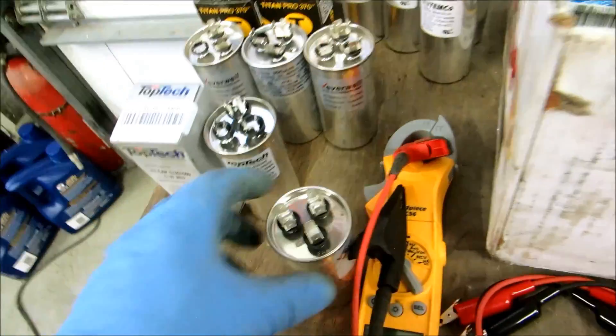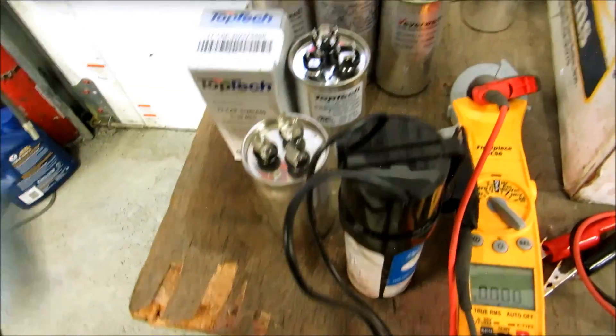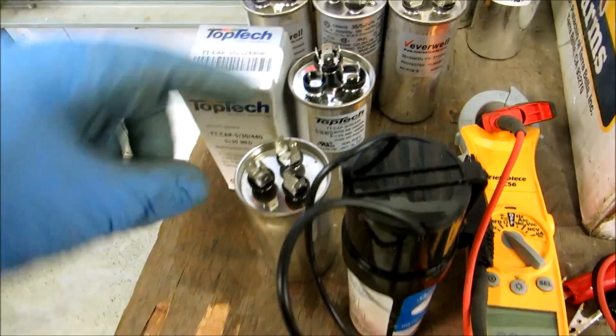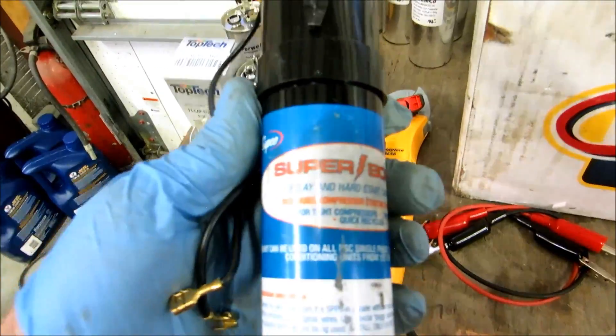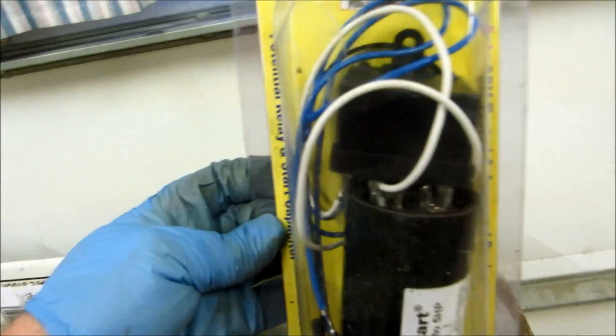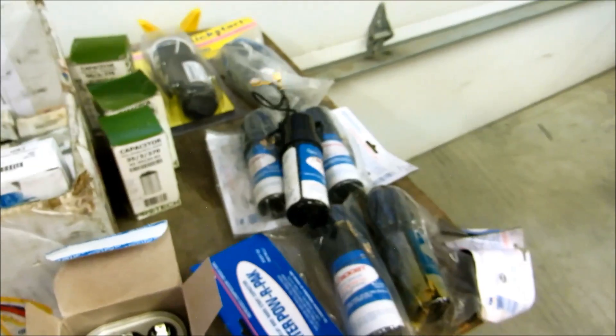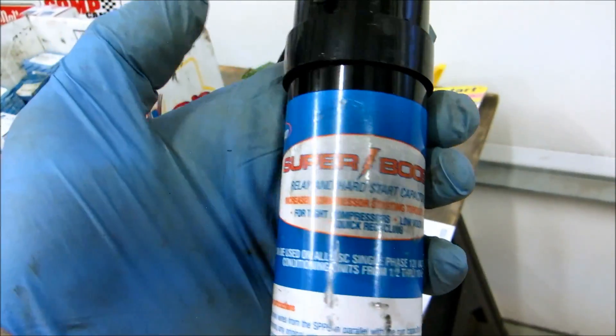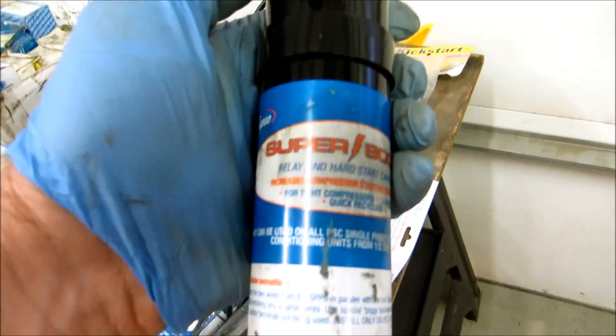Now on a hard start kit like this Supco, once it's all wired you just put one lead on common and one lead on compressor, and this is going to give the compressor a boost to help it start. You got the three-wire ones with relays - these are good. Hard start kits are two-wire; both of these are two-wire hard start kits, but the five-two-ones are five-wire. They get a relay; these got a resistor that's supposed to drop out on the inside. I will use these in a pinch - I've had a couple of them explode on me but for the most part they're not too bad.